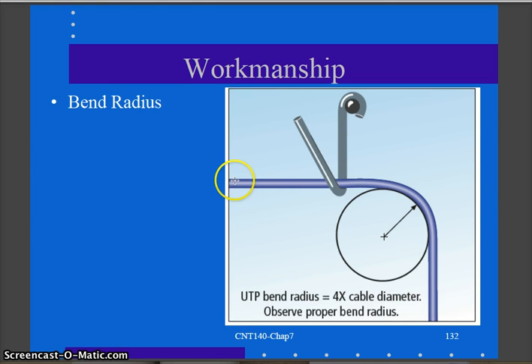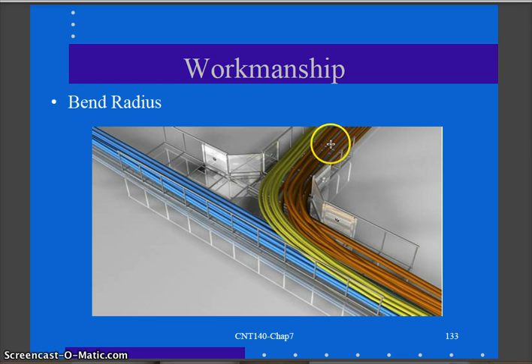This is what they're showing here. As the cable goes around a corner, I need to make sure I'm adhering to this 1 inch bend radius, or 4 times the cable diameter.